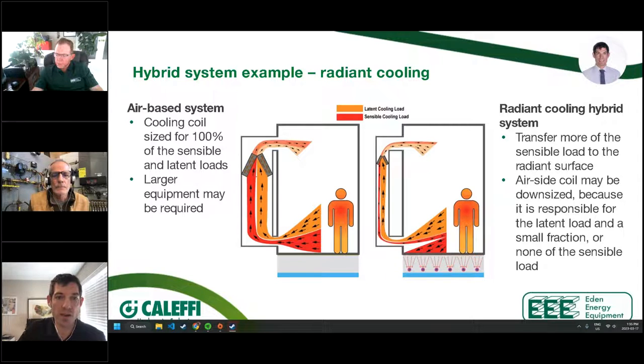So the graphic on the left would be an all air way to do the latent and the sensible loads. You're going to take all of the energy out of the room, go through the coil and bring it back a little bit cooler. In this scenario, we've got bigger ductwork because we have to deal with 100% of the latent and the sensible.